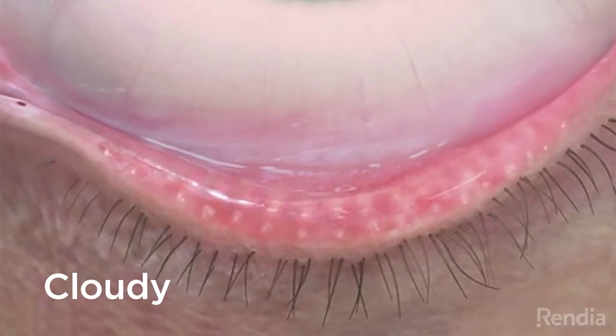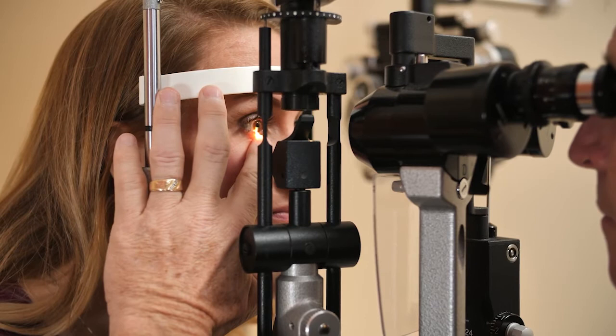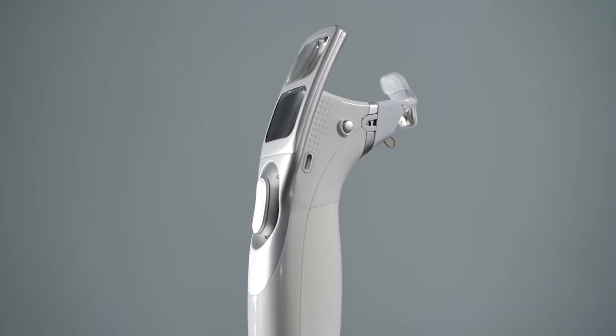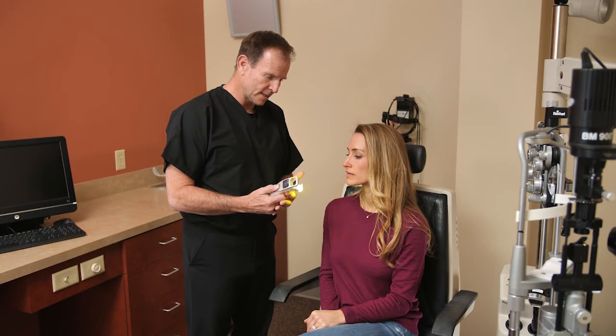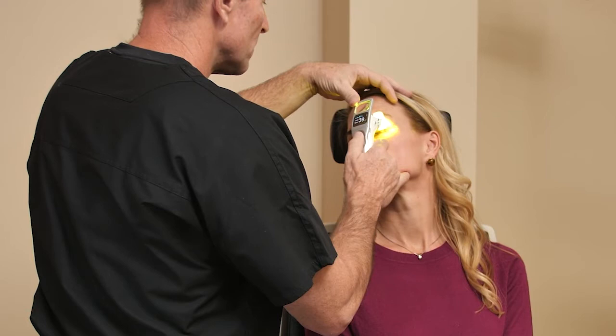Healthy meibomian glands produce clear and liquid meibum. Dysfunctional glands produce meibum that is either cloudy or thick and paste-like. In some cases, the glands do not express any meibum when compressed. This may indicate fully blocked, capped, or damaged glands. The Systane iLux system allows eye care professionals to target dysfunctional glands and improve signs and symptoms of MGD using localized heat followed by compression therapy. The device is positioned on the eyelid, light-based heat melts the meibum, and compression expresses the unhealthy meibum. When the blockage is cleared and healthy meibum is seen on the lid margin, the procedure is complete.